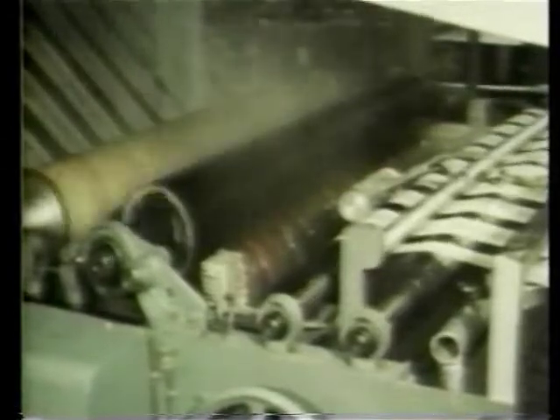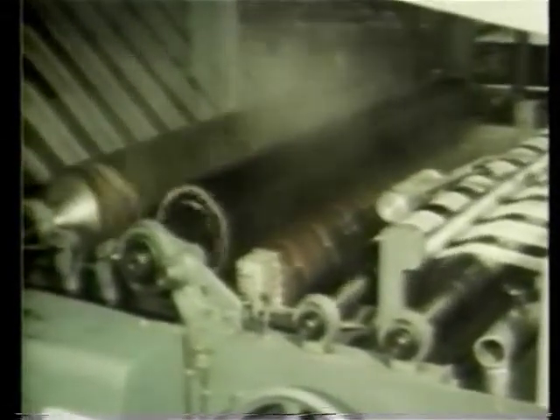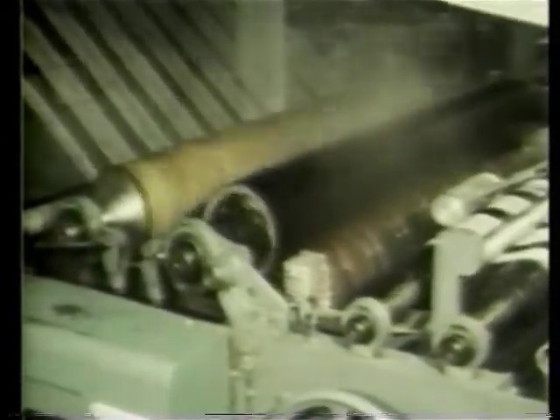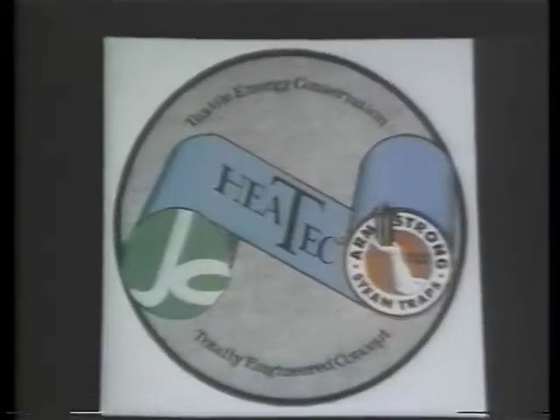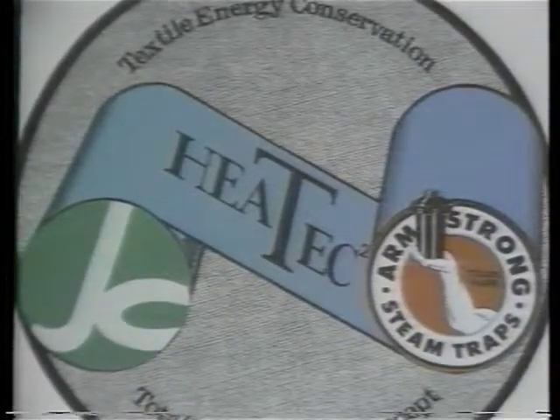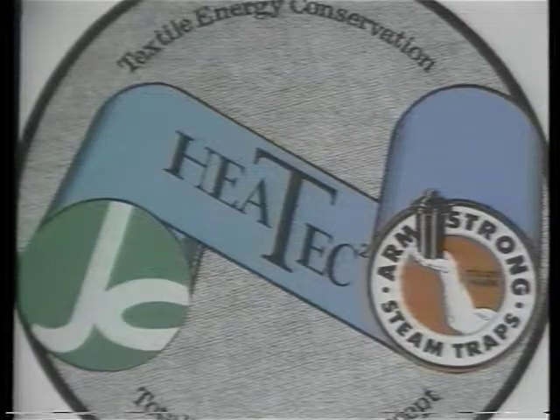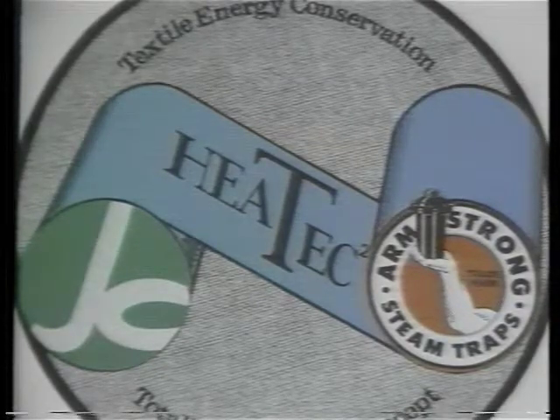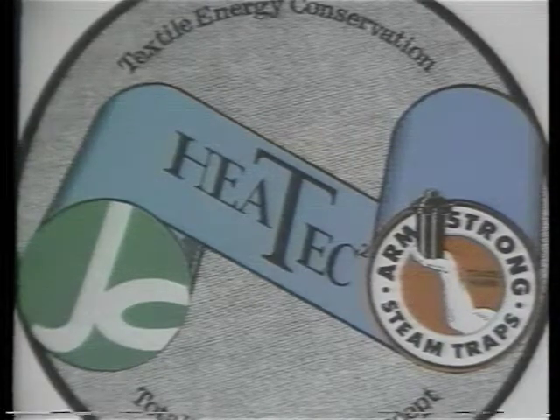Since large volumes of air are often present in these rotary cylinders, particularly on startup, it is recommended that the inverted bucket's air handling capabilities be supplemented by an external thermostatic air vent. In response to the demand for ever-increasing production rates and considering the spiraling cost of energy, a new steam and condensate drainage system has been specifically designed for the steam-heated rotary cylinders found in the textile industry. The Armstrong-Johnson Heat-Tech system has proven effective.